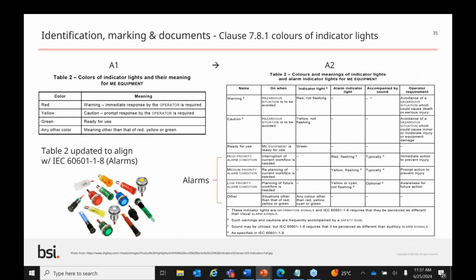So table 2 is a huge improvement from the previous edition. It is much clearer and shows what is expected for cautions, warnings, and alarms. The table was developed by the Alarms Committee, SC62A, Joint Working Group 2, who's in charge of the alarm standard 60601-1-8. The significant change is the 3 alarm rows are totally new, as there was no previous guidance there, and added in clarification for the other colors row at the bottom of the table.